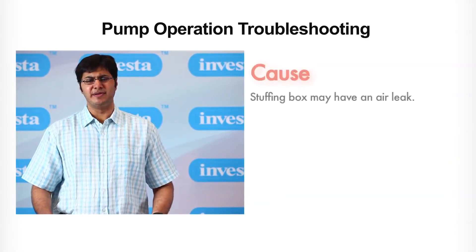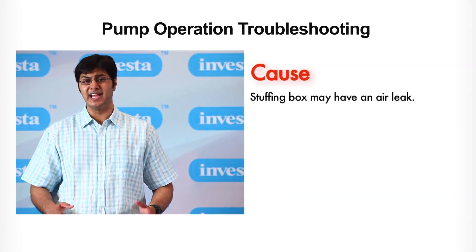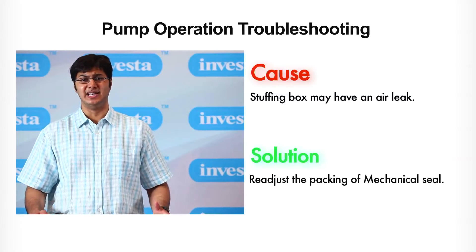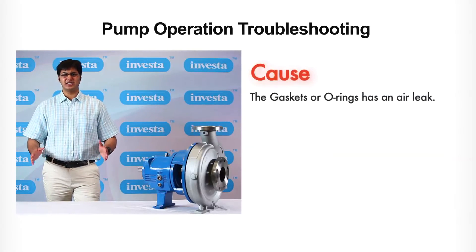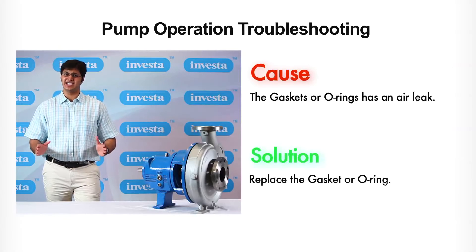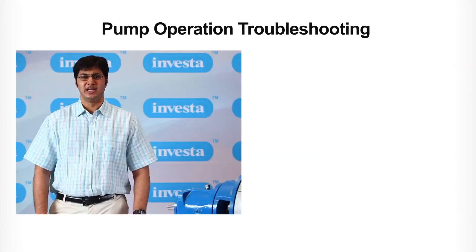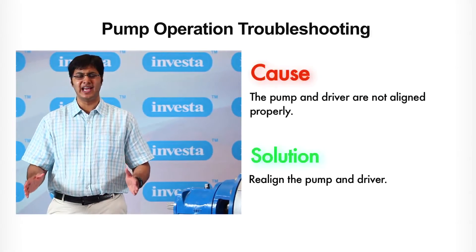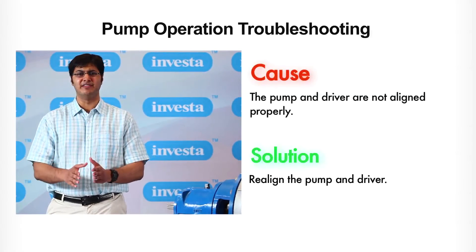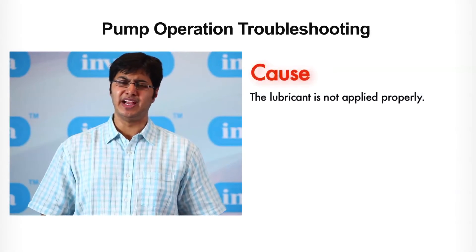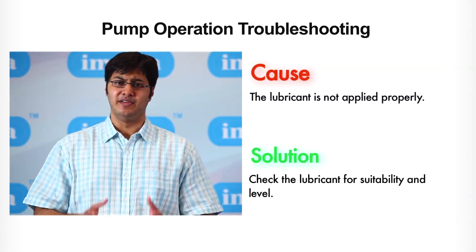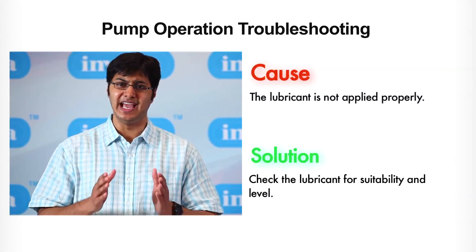Number six: the suction lift is too high — shorten the suction pipe. Number seven: stuffing box may have an air leak — re-adjust the packing of the mechanical seal. Number eight: the gaskets or o-rings may have an air leak — replace the gaskets or o-rings. Number nine: the pump and driver are not aligned properly — realign the pump and driver. Number ten: the lubricant is not applied properly — check the lubricant for suitability and level.